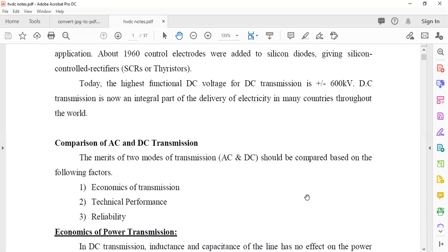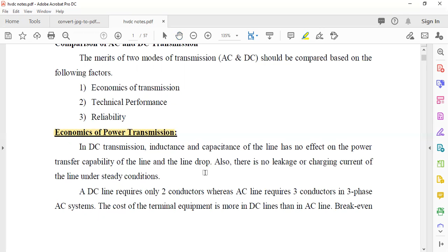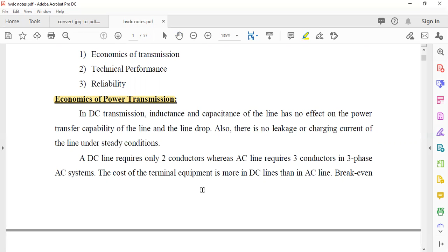In DC transmission, inductance and capacitance of the line have no effect on the transfer capability of the line and the line drop. So there is no leakage or charging current of the line under steady state conditions. A DC supply requires only two conductors, whereas AC supply requires three conductors in a three-phase AC system. So in terms of economics, we are using two conductors in DC and three conductors in AC supply. The cost of terminal equipment is more in DC lines than in AC lines.